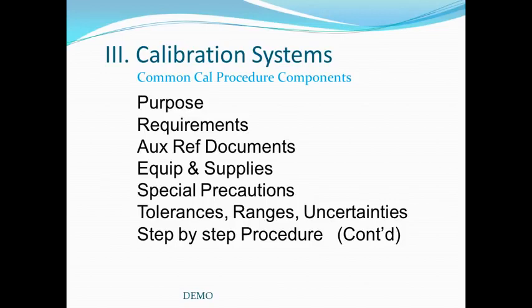Secondly, the requirements for the procedure. You should reference any auxiliary documents, such as ISO 17025 or Z540.3. You should list the equipment and supplies that are required to do the calibration. Also list right up front any special precautions, such as high voltage in electronic circuits, or high pressure in pressure calibrations. Tolerance, ranges, and uncertainties should be listed for the various calibration items. A very important part of that procedure is the step-by-step procedure, which directs the technician through the calibration procedure in a manner which will assure good calibration.